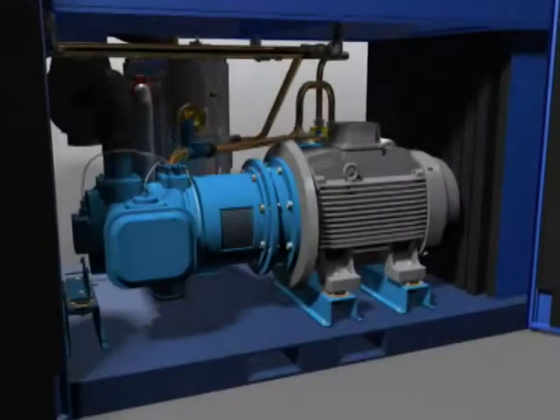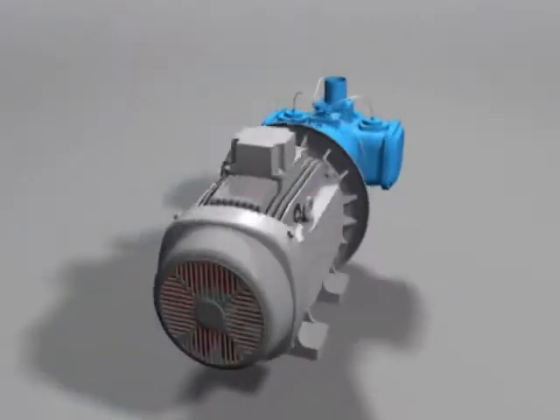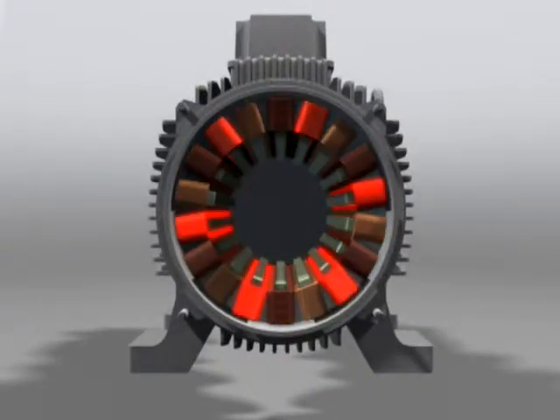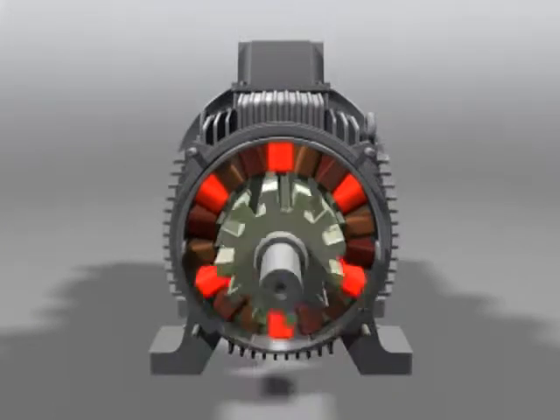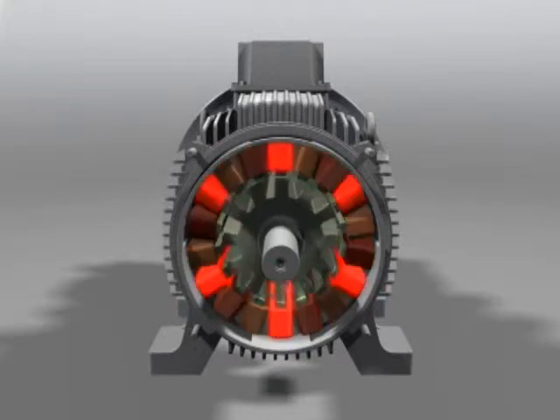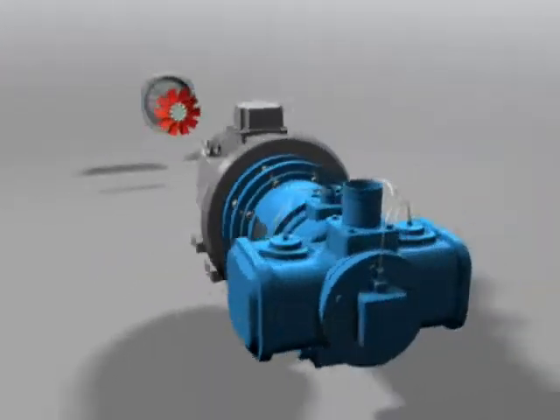The compressors can be driven by a fixed-speed motor, an inverter, or by our innovative switched reluctance drive system. Using the SR drive system, the digitally controlled three-phase motor enables the speed of the motor and thus the volume flow of the compressor to be precisely controlled to meet your changing demands. Fine pressure control ensures that you use exactly the energy required to do the job and no more.